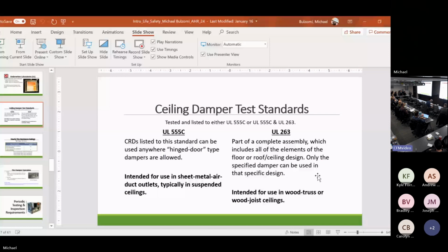Damper industry came along and said, no, we can build those better. We want to do a comparison test. Wherever you allow a hinged door type damper, we want a UL 555C damper allowance. That's why you can put in a lay-in ceiling diffuser with a nailer damper and a thermal blanket you bought from Ferguson, or I can buy a fire rated package diffuser from Price Industries and pop that in there, and that's got a thermal blanket, a ceiling radiation damper, and a diffuser, all the same thing. Those are UL 555C applications. It doesn't matter whose damper goes where, as long as it's a 555C rated damper, meets the requirements.